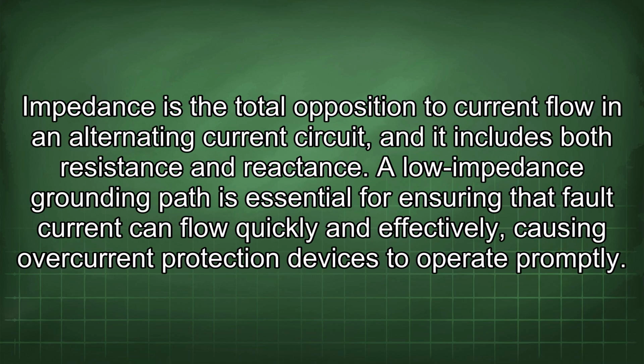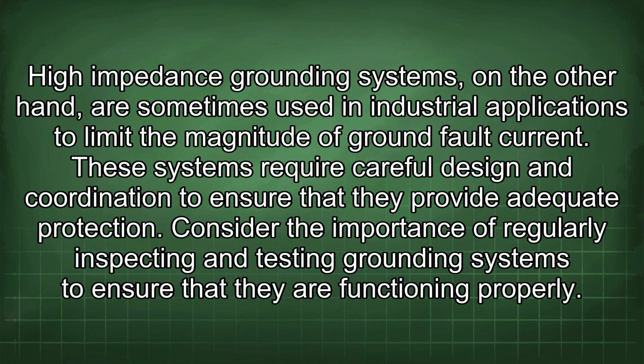Impedance is the total opposition to current flow in an alternating current circuit, and it includes both resistance and reactance. A low impedance grounding path is essential for ensuring that fault current can flow quickly and effectively, causing overcurrent protection devices to operate promptly. High impedance grounding systems, on the other hand, are sometimes used in industrial applications to limit the magnitude of ground fault current. These systems require careful design and coordination to ensure that they provide adequate protection.